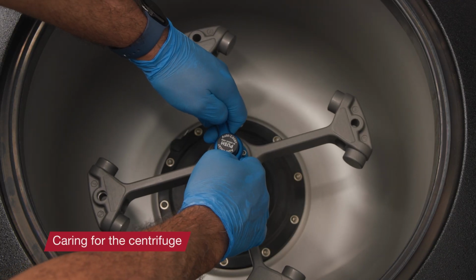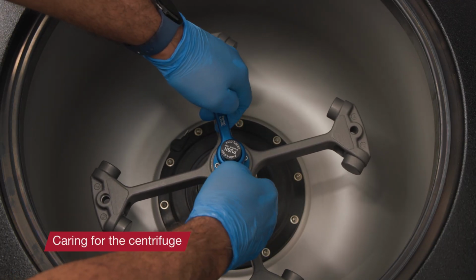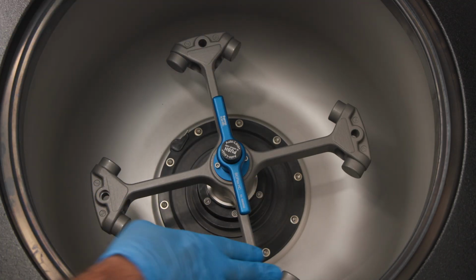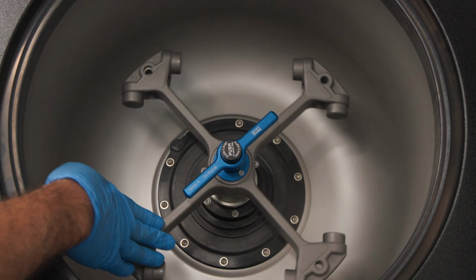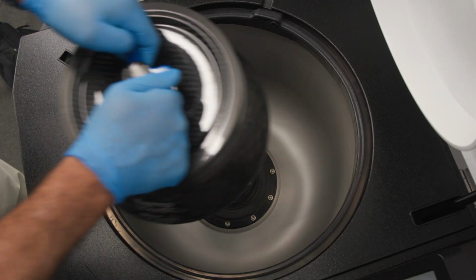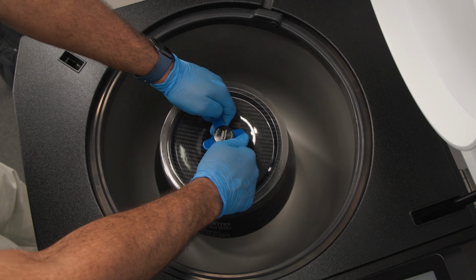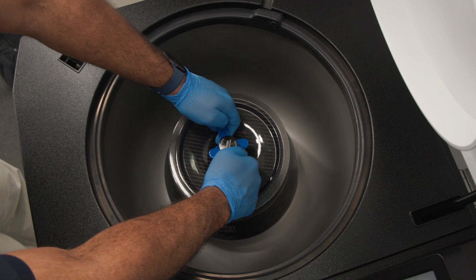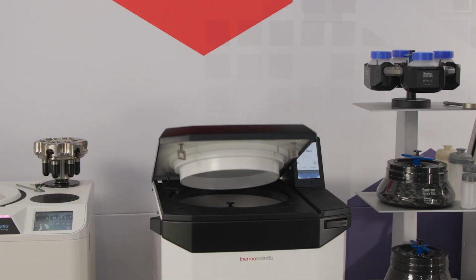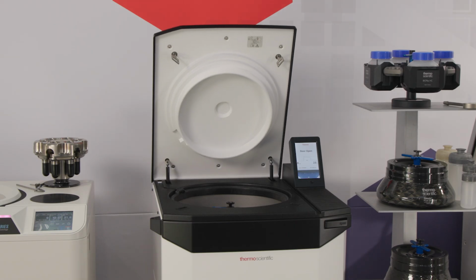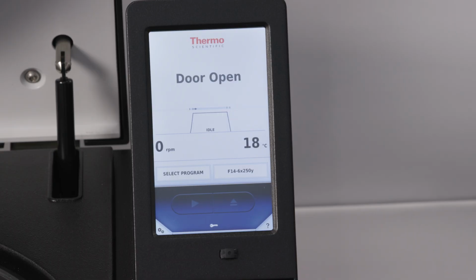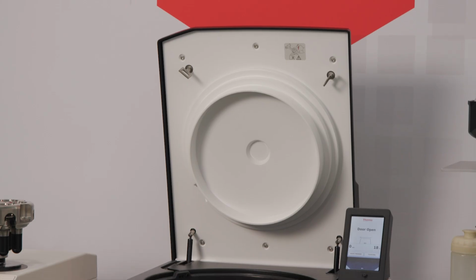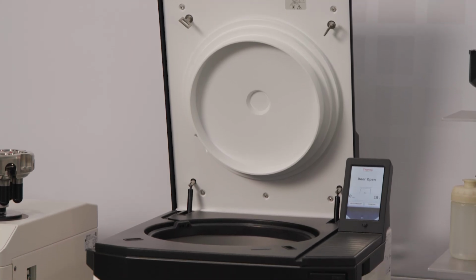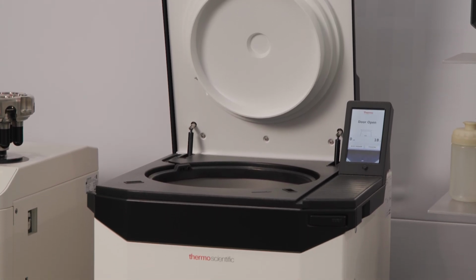Do not allow liquids, especially organic solvents, to get on the drive shaft, drive bearings, or centrifuge door lock. Organic solvents break down the grease in the motor bearing, damaging the drive and door lock. When you're not using the centrifuge, keep the door open or turn off the power. This helps prevent corrosion and mold growth within the centrifuge chamber. This practice helps maintain the equipment's performance and longevity.